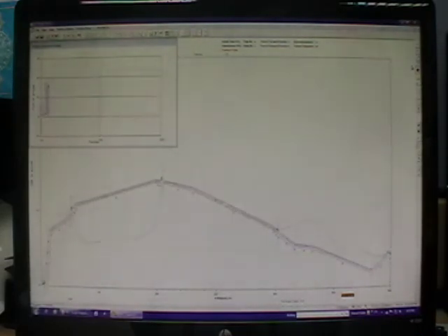At the same time, there are pressures being exerted at the pump, as you can see on the left. In the smaller screen on the top left there, what you see is the pressure head versus time. So that's the transient plot. The one in blue, which you see spiking up and down, that's at the pump. So very clearly it shows that there are pressures building up and easing as the waves come back and forth in the system.